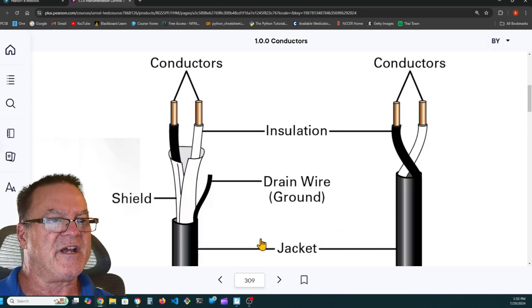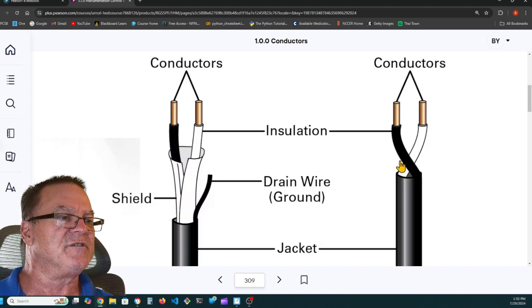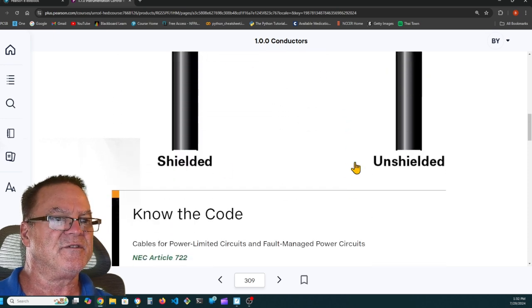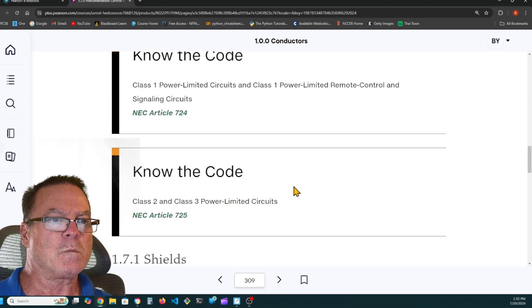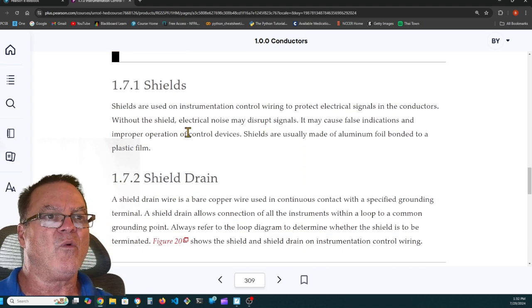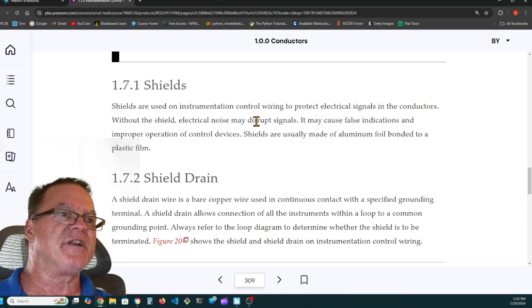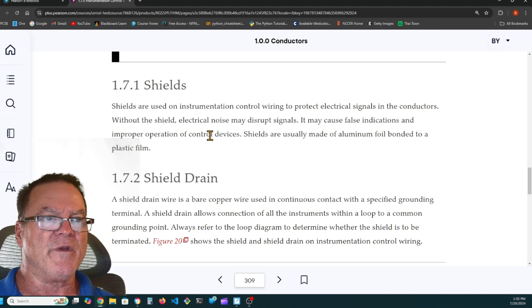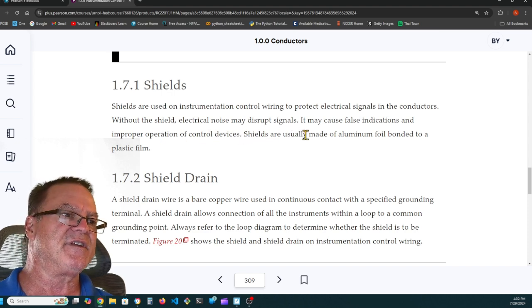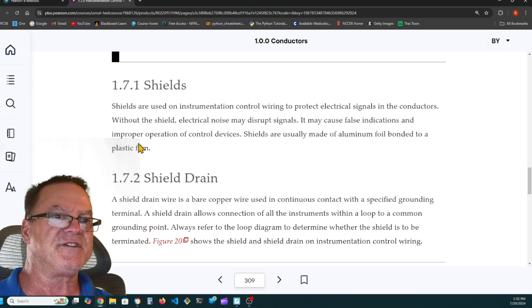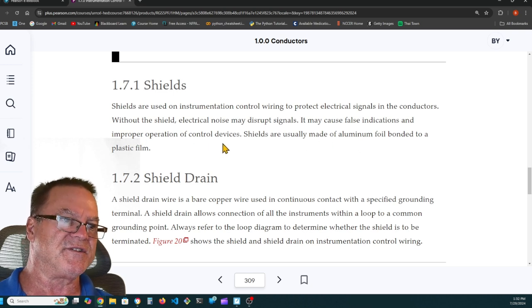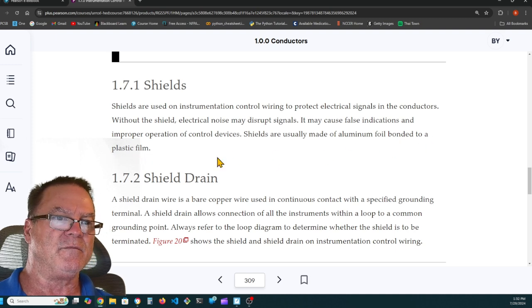So here's the outer jacket. Here's a drain wire and a shield. This one's non-shielded, just has 2 conductors. There's a shielded and unshielded. 1.7.1 Shields. Shields are used on instrumentation control wiring to protect electrical signals in the conductors. Without the shield, electrical noise may disrupt the signals. It may cause false indications and improper operation of control devices. Shields are usually made of aluminum foil bonded to a plastic film.